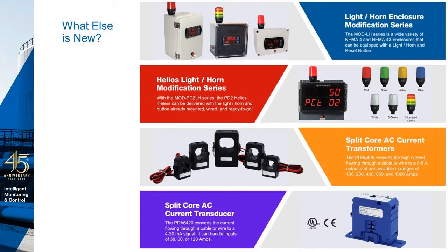Or if you like to stay in the world of 4 to 20 milliamps but still need to measure high current, we've got split core current transducers, which are low-powered devices that output a 4 to 20 milliamp signal for up to 120 amps. Those can go right into meters like our ProView or any of the other 4 to 20 milliamp products you regularly work with.